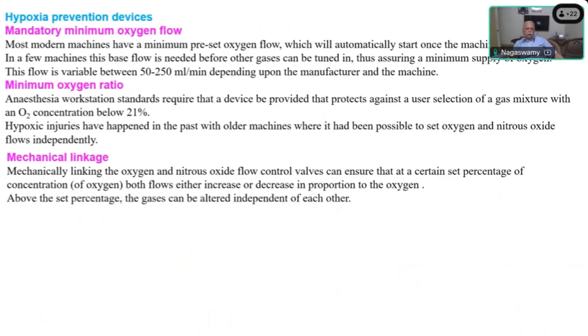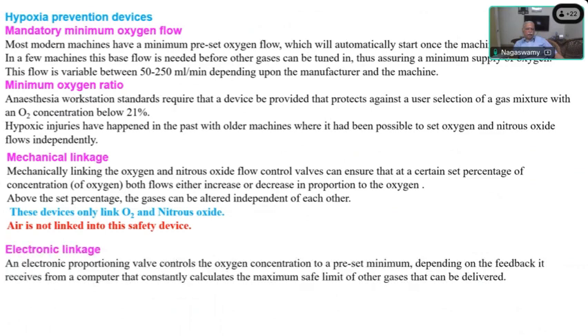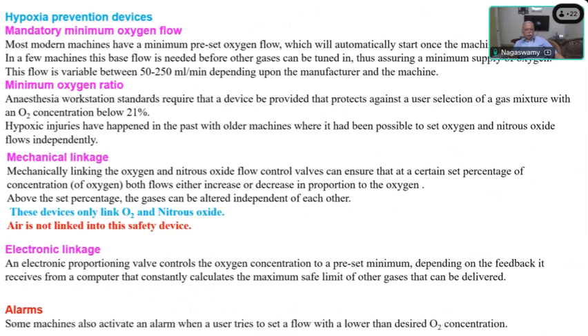Then there is a mechanical linkage, which of course he mentioned. And these devices are not linked to air, only to oxygen and nitrous oxide. Nowadays we are commonly using medical air. Air is not linked to the safety devices because air itself contains oxygen. That is the reason why they have linked only oxygen and nitrous oxide. And there is an electronic linkage which proportions the oxygen concentration to a preset minimum, depending upon the feedback. And there are alarms which give you an audible caution that the oxygen level is going down.